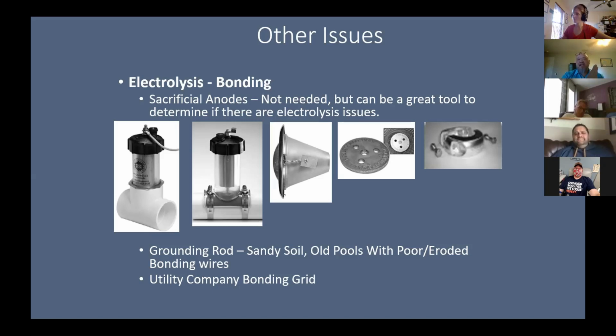And the reason why I say that, a sacrificial anode is only there as a Band-Aid or as a diagnostic tool. If that sacrificial anode starts deteriorating, you've got a bonding issue. And the reason why you're going to see the deterioration of a sacrificial anode is because it's typically a softer metal than your brass, copper, and stainless steel. So when you see that deteriorating, it's because that electrical charge that's in the water is looking to discharge. It doesn't have an electrical bond, so it's going to try to find that soft metal first to attack. Okay, so it's a great tool to let you know that you've got electrolysis issues, but it's not the solution.